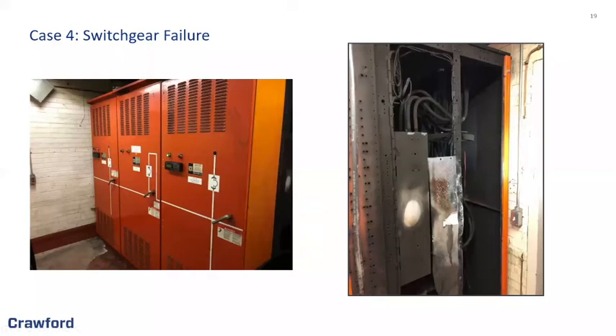The fourth case I'll discuss involves a switchgear failure, again at a hospital. This was an arcing and minor explosion within the automatic transfer switch. Here is the cabinetry for the switch, and these were the damages inside. As you can see, all the internal components were basically destroyed and required replacement. The switch transfers power to the backup generator in the event of an outage at the hospital.